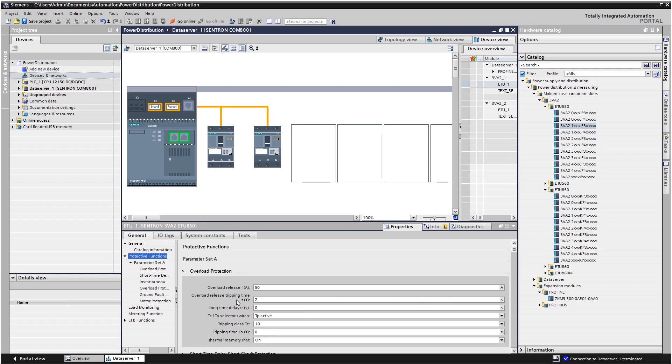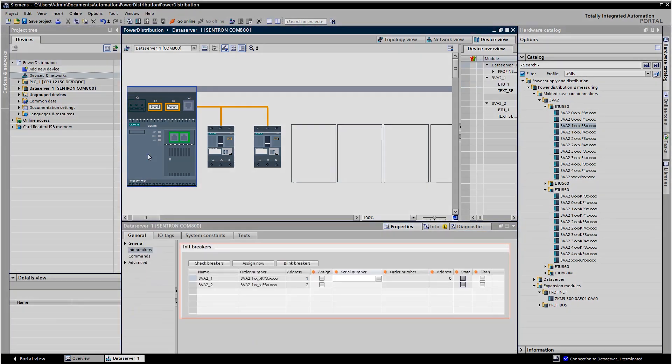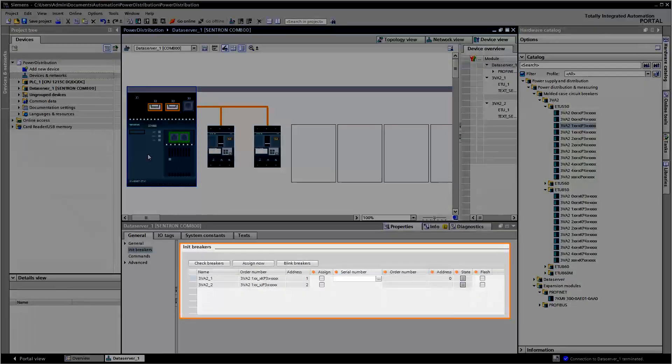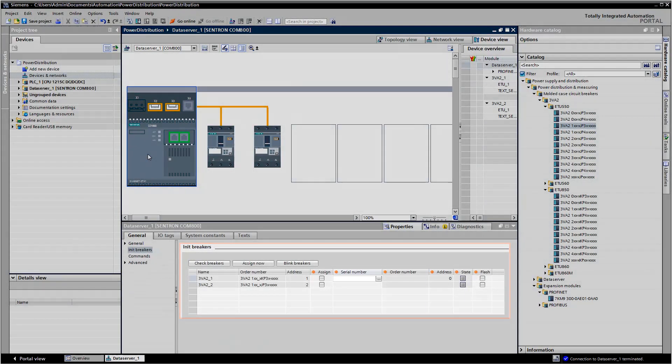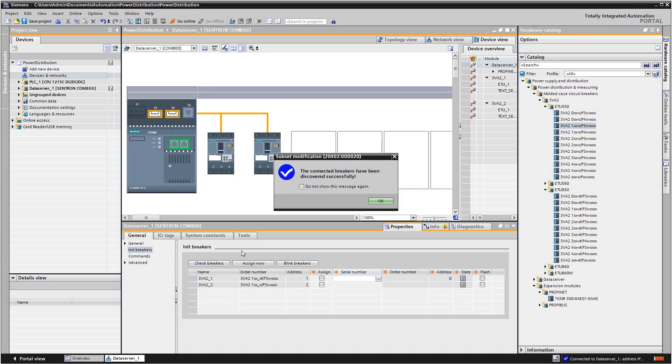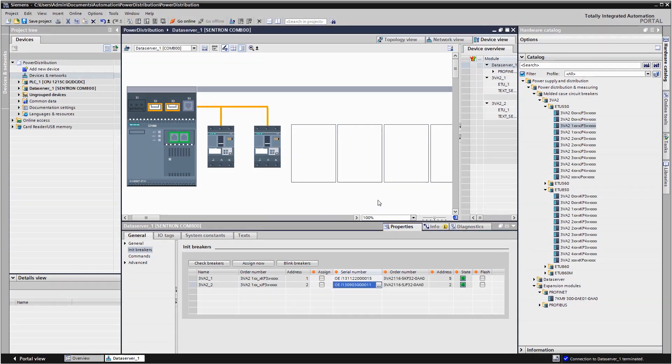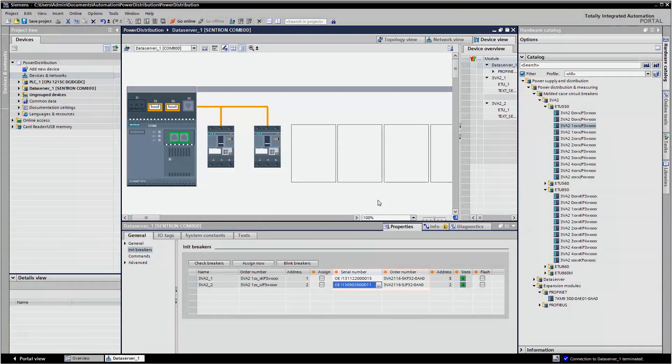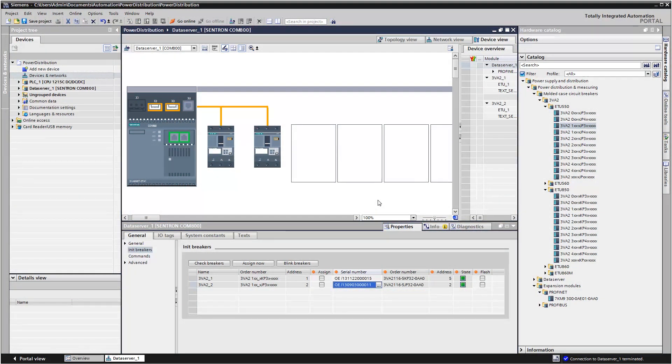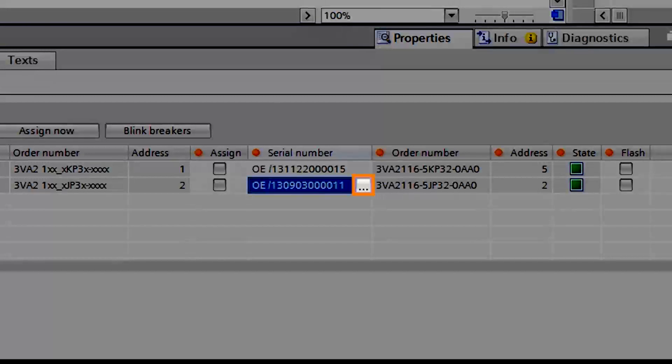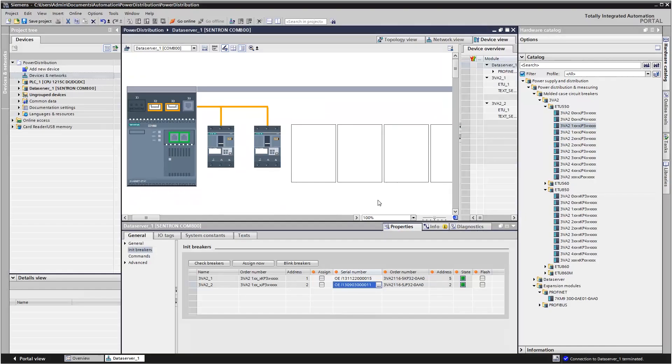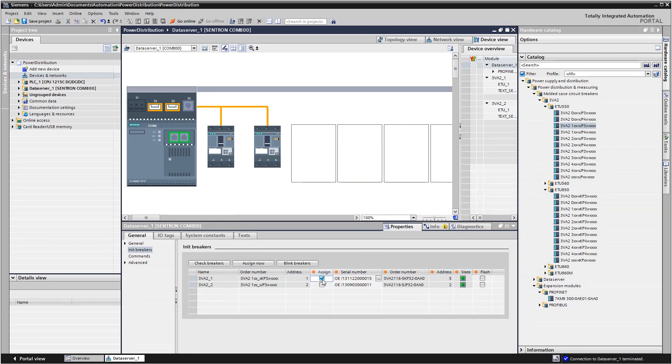Once you have parameterized the devices, the configuration needs to be assigned to the devices using the initialization function. It is assigned automatically if devices can be assigned based on their order number. Use the selection dialog to specify this assignment if several identical types of devices are connected to your breaker data server.